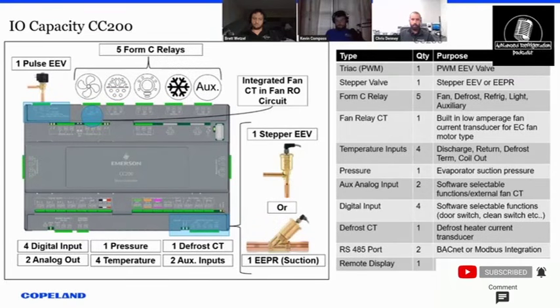Along the top, we've got 5 relays. 4 of them are predefined for fan, defrost, lights, and refrig. And we have 1 auxiliary that can be programmed as a backup for any of the 4, but that can also do some additional functions. One of those additional functions is it can be a satellite for E2 or E3. If we put it in satellite mode, it just becomes directly controlled by E2 or E3. So any flex combiner you link it to, it will just listen to whatever E2 or E3 tells it. Also on the relays, we have the integrated fan CT in the fan RO circuit.